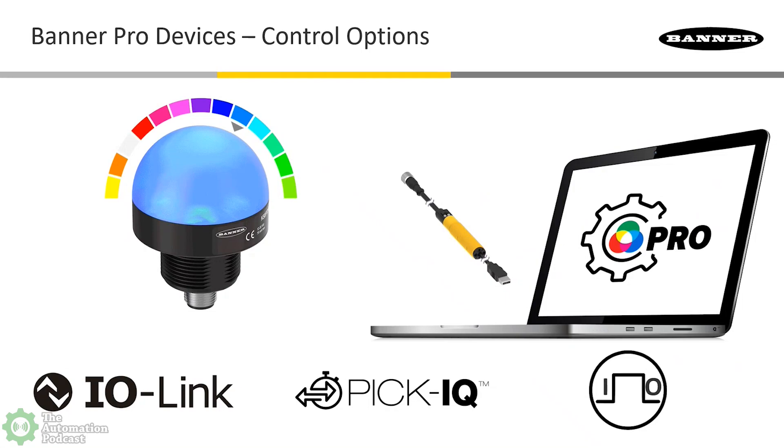Yeah, we've got a few documents out there and a few other videos, maybe tucked away a little more in the Banner archives than they should be. But we can help users get going with this very simple register set. Back to IO-Link — we put a couple of things in parameter data, essentially picking the run mode you want to be in. With a few more registers you're choosing your colors on the fly, giving that dynamic indication capability. We do allow for mixed IO — you could go BCD, some binary IO on the discrete side. State one can be a single wire, but state two can be multiple wires. So we maximize what we can do with the pin count and still give flexibility for users who like discrete IO or just aren't going to change their machine architecture for the sake of a cool new light.